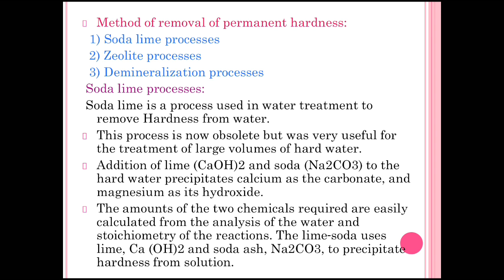This process is now obsolete but was very useful for the treatment of large volumes of hard water. Lime means calcium hydroxide (Ca(OH)₂) and soda means Na₂CO₃. When lime and soda are added to hard water, they precipitate calcium as carbonate and magnesium as hydroxide. The amounts of the two chemicals required are easily calculated from the analysis of water and stoichiometry of the reaction.